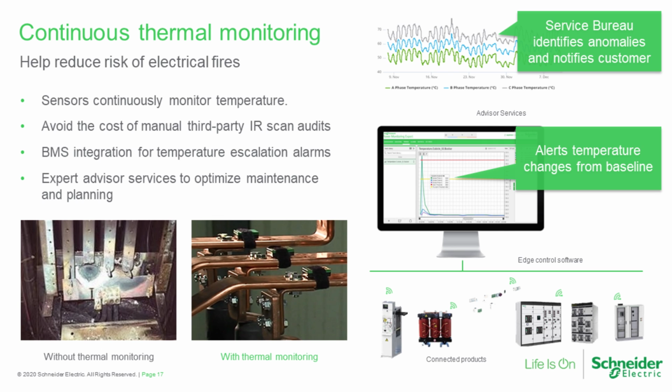Companies come out and do a full scan of your equipment using infrared technologies and then assess the risk of maybe overloading, creating a fire, things like that. What we have found is this periodic test, firstly, is expensive, and secondly, it's a reactive mechanism. It's not really a proactive, predictive way.